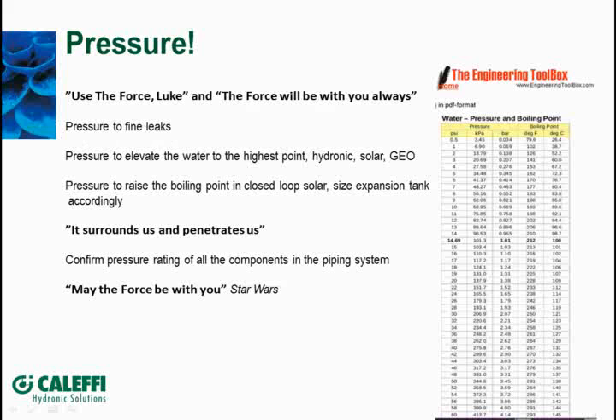But the other thing that pressure can do for you is elevate the boiling point of the fluid. I learned this lesson when I went over to Europe a couple years ago, and I was looking at some solar installations over there. We went around to some commercial buildings, and I noticed the gauges. Of course, they read in bar over there, and these systems were reading about 4 bar, which is about 15 pounds per bar, so that gives you about 60 pounds fill pressure on these glycol systems. Gosh, that's odd. Typically on a residential system, we fill a system up somewhere between 15 and 20 pounds, depending on the height of the building. And they said, well, the reason we do that is we try to get the boiling point of that fluid up. The more pressure you put on the fluid, the more you raise the boiling point of it.